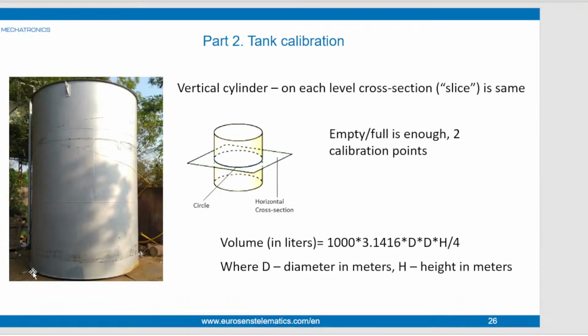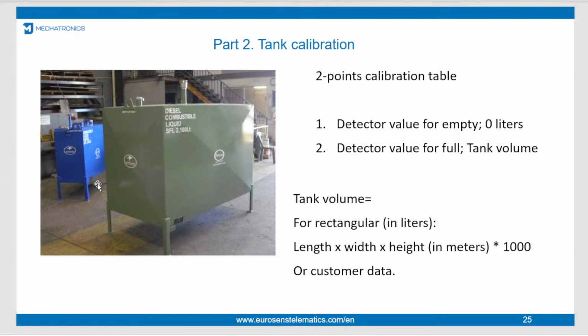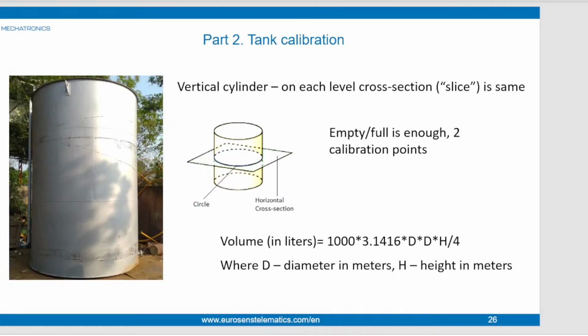By the way, regarding cylinder tank shape, yes, for a horizontal cylinder we need a lot of calibration points. But what if we have a vertical cylinder? How many calibration points do we need? If we check the cross section, it's the same for all levels. That means for a vertical cylinder, again we need only 2 calibration points, empty and full. And again, we don't need to fill it till full to make the tank calibration. We can calculate the volume using a school formula. So these kinds of tanks are very easy to calibrate because you don't need to do it physically.